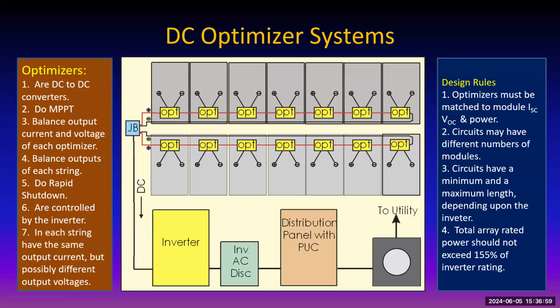Circuits may have different numbers of modules. Why is that? Very simple, because these things are maximum power trackers. In order to maintain balance at the string level and the same voltage, the strings will adjust their currents. You add up all the powers of all the optimizers in the string and divide by the voltage that the inverter is telling them to operate at, and that tells you the string current. It's just that simple. You do that same thing for every single string, and that tells the optimizers what voltages they have to operate at in order to produce the amount of current that's necessary.